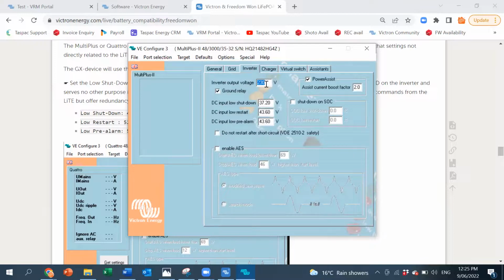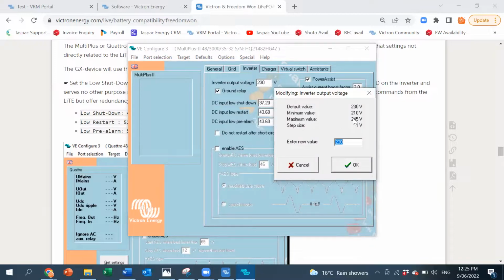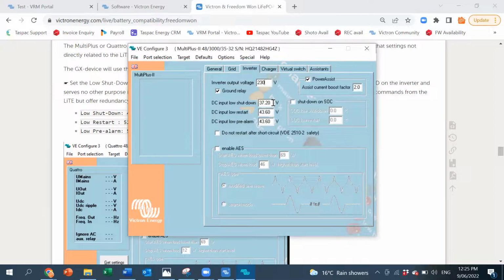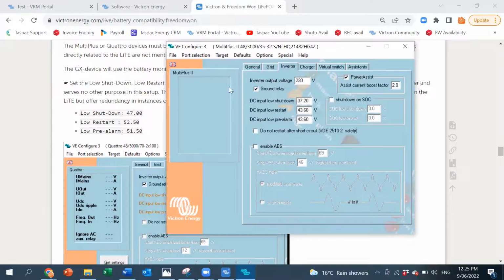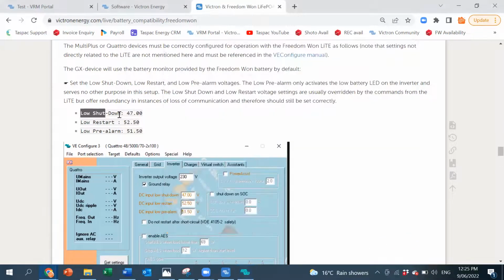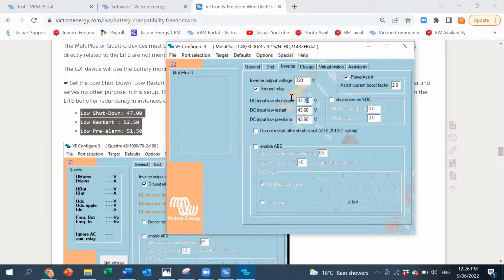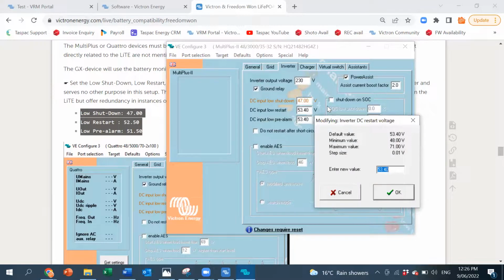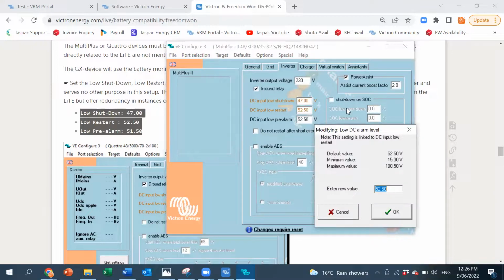The inverter itself, how many volts is it putting out? You can legally put that up to 245, or actually 246 in New Zealand. If you've got a long run between the inverter and the house, maybe you want to put that to 240, so they've got good voltage at the house. But you can change that as you see fit. Now here we come to voltages. So we've got low shutdown here. See there in the background, we've got shutdown 47. So we'll put that in there, 47. And we'll just copy these, low shutdown restart, 52.5. And pre-alarm will be 51.5.